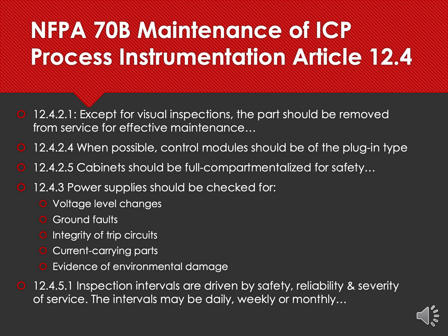Let's take a look at the maintenance requirements of industrial control panels as outlined by the NFPA 70B. Now, of course, I'm just going to hit the high points here in this discussion. You would, of course, want to do a full reading of this if this applies to you in your operation. The first point they're going to make is that other than just visual inspections, they believe that parts should be removed from service in order to effectively perform maintenance on them. Now, again, that's up to you in your operation as to whether that's relevant to you, but that's their suggestion. The second point will be that control modules should be of the plug-in type if possible. This is not only for expeditiously changing them out of service, but also for safety.